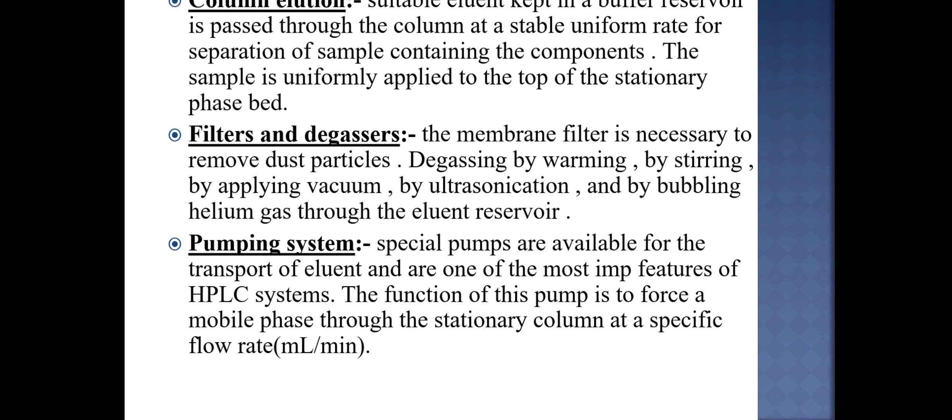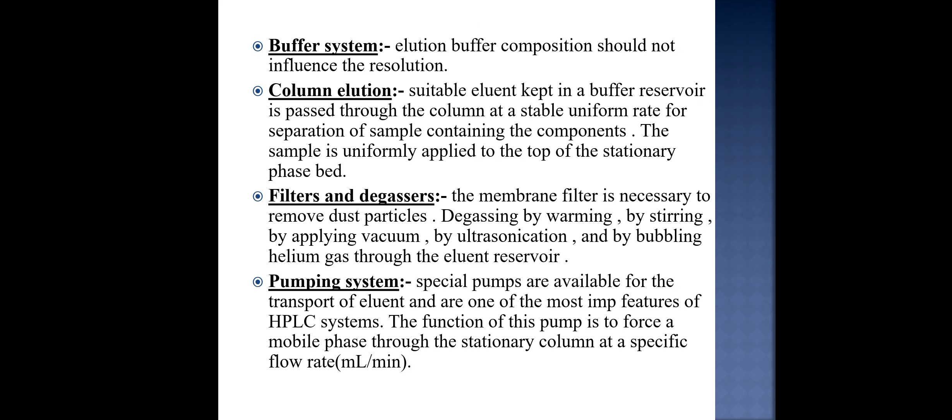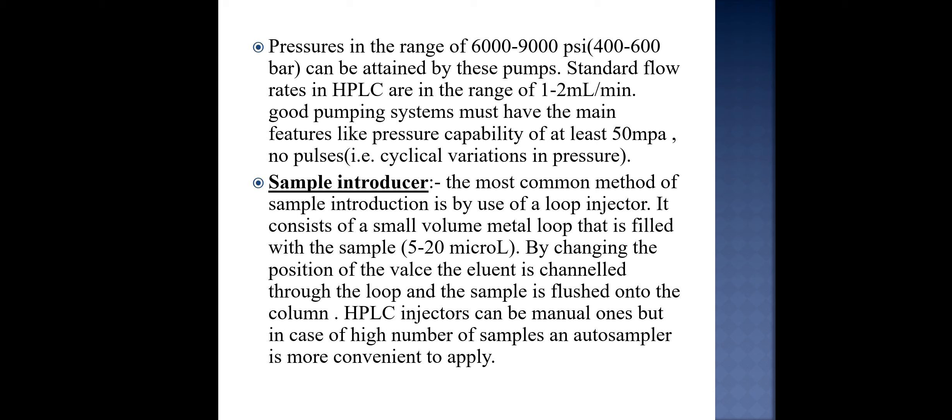Pumping system. Special pumps are available for the transport of eluent and are one of the most important features of the HPLC system. The function of this pump is to force a mobile phase through the stationary column at a specific flow rate which is ml per minute. The pressure ranges are 6000 to 9000 psi or 400 to 600 bar and can be attained by these pumps. Standard flow in HPLC is in the range of 1 to 2 ml per minute. Good pumping system must have the main features like pressure capability of at least 50 MPa and no pulses must be there and cyclical variation in pressure must not be present.